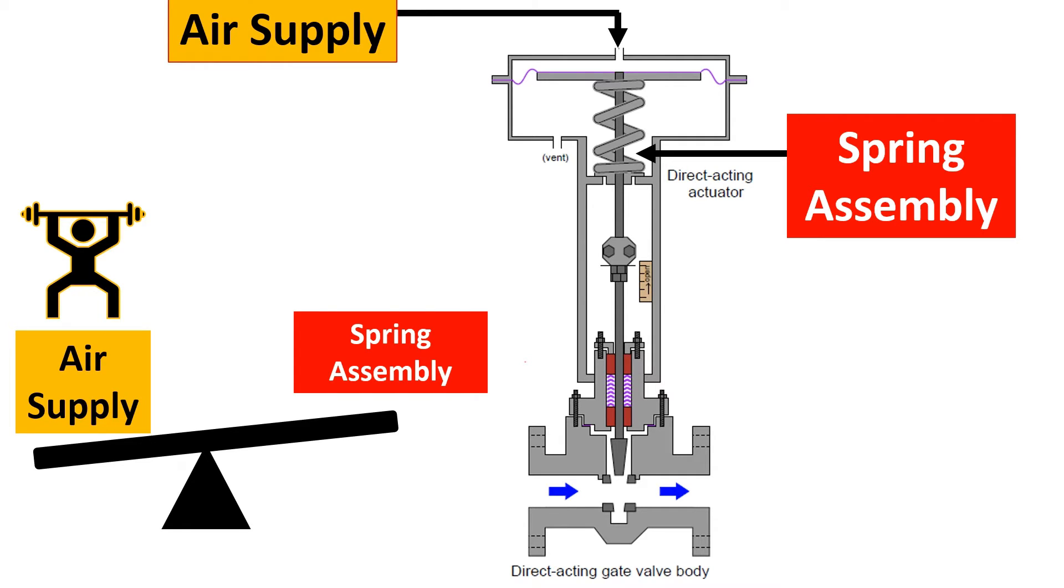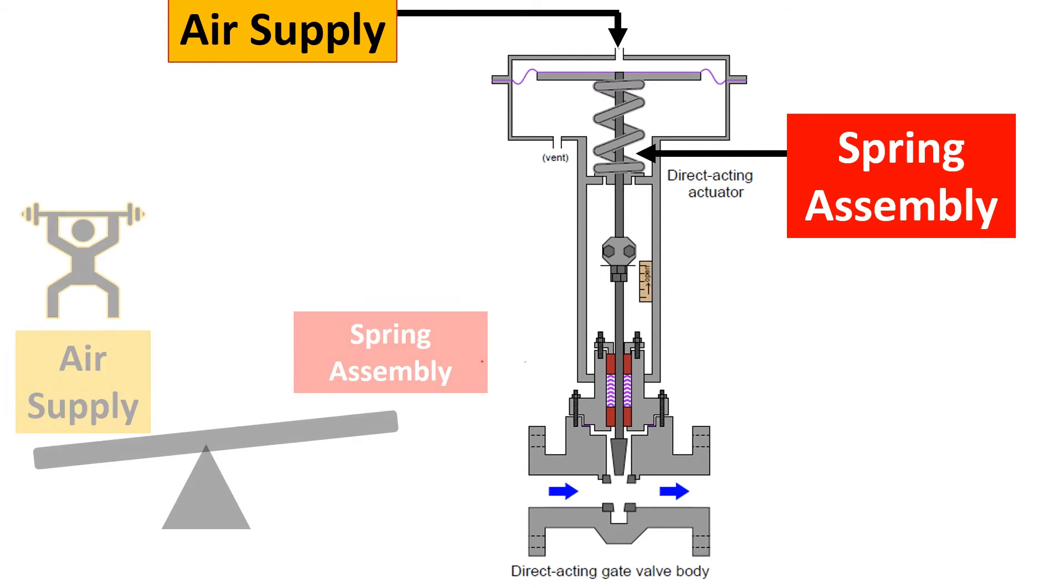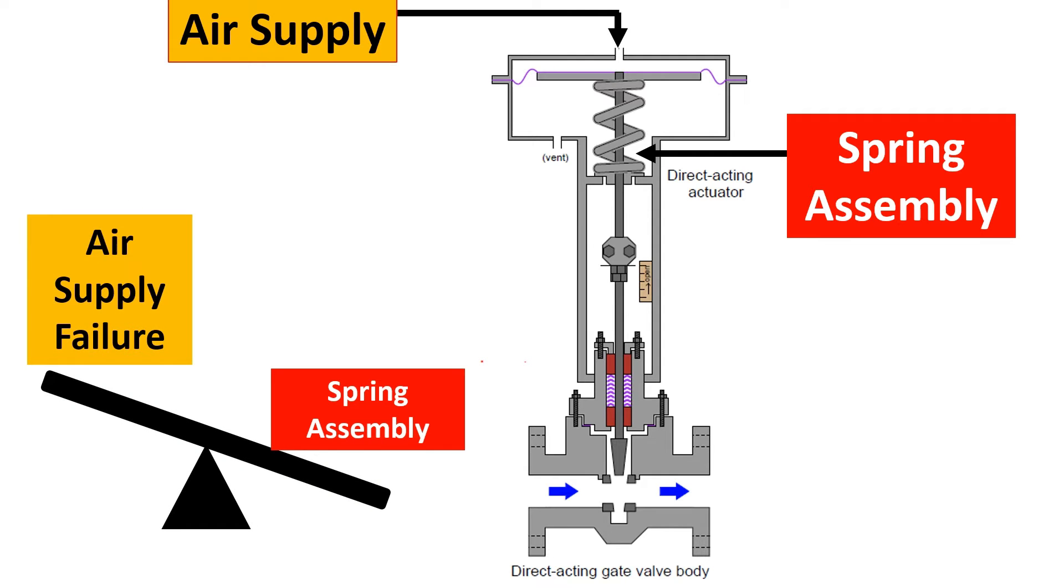Air supply has an upper hand, but now imagine in the opposite direction where the air supply has failed. So the spring assembly is going to now have an upper hand and the spring assembly will direct the valve to its failure mode which could be fail open or fail close.